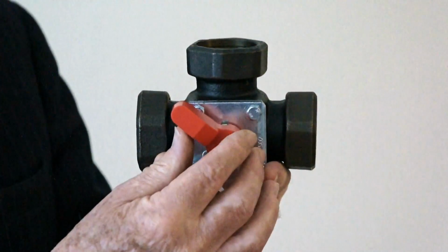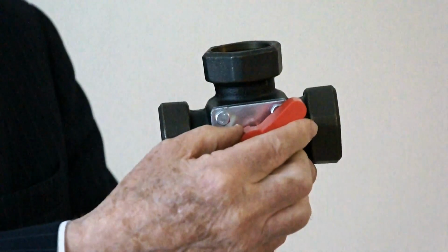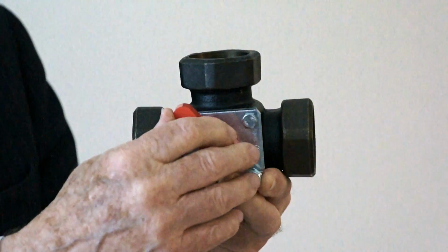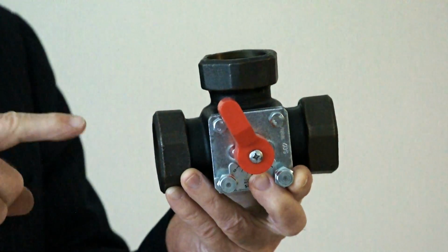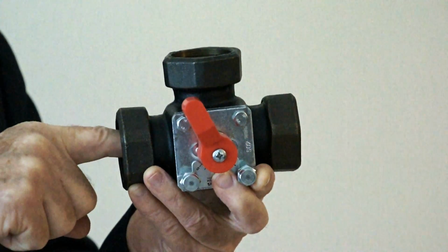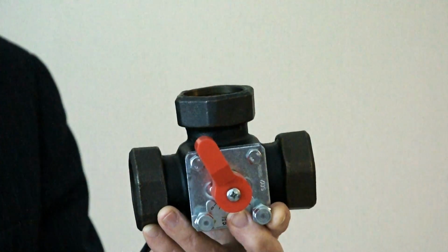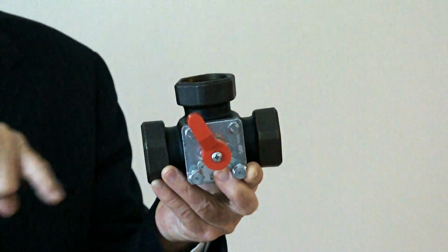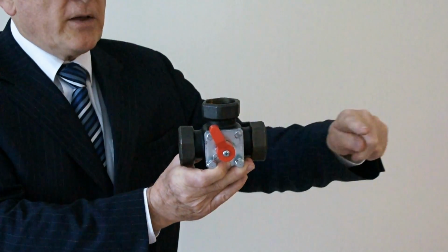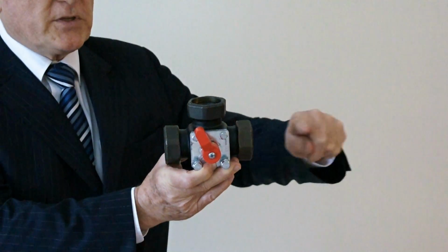So by moving this particular lever, and of course in the real world this will be the actuator we saw earlier on, at different points we can divert the water from the boiler through this particular port, through this top one back to the boiler. That is called a bypass. So we're just circulating that hot water back, and then we are proportionately allowing a certain amount of the hot water on the flow of the boiler to come out through this particular pipe.